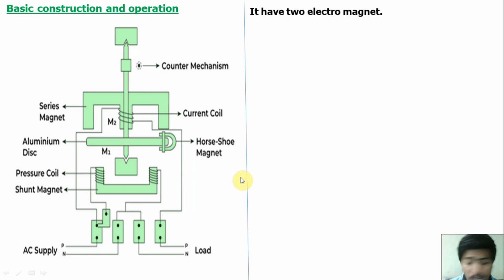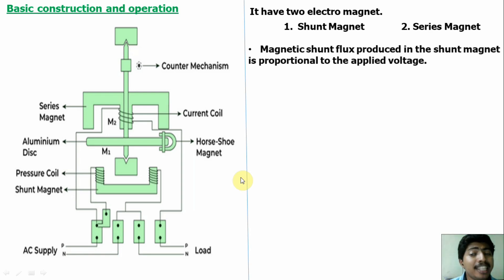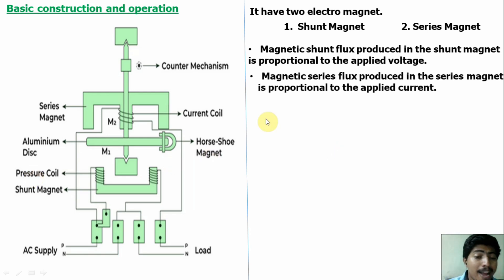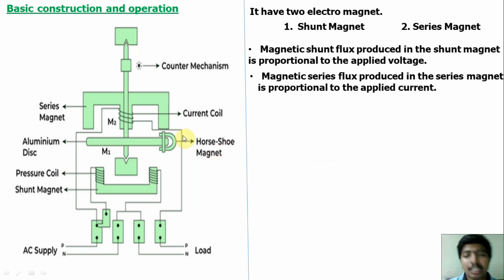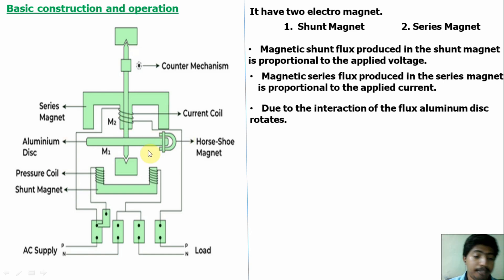It has two electromagnets. One is the shunt magnet and another one is the series magnet. The magnetic flux produced in the shunt magnet is proportional to the applied voltage. The flux produced in the series magnet is proportional to the applied current. So it has two fluxes: shunt flux depends upon the applied voltage, and series flux depends upon the current. Due to the interaction of the two fluxes, the aluminum disc will rotate.